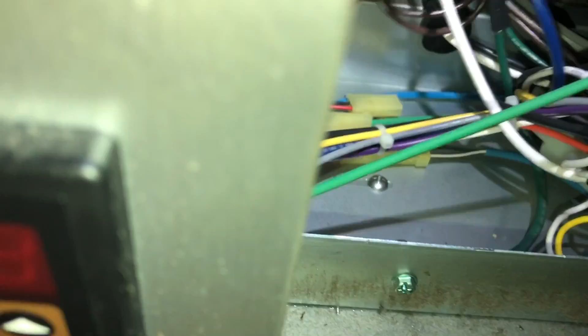Blue is the evap sensor. Now I got this. I'm going to stick a temperature probe where the probe of that cabinet sensor is, right there on the wall. Let's zoom in. And then we'll get the ohms reading off of this sensor here and see if this sensor went bad.